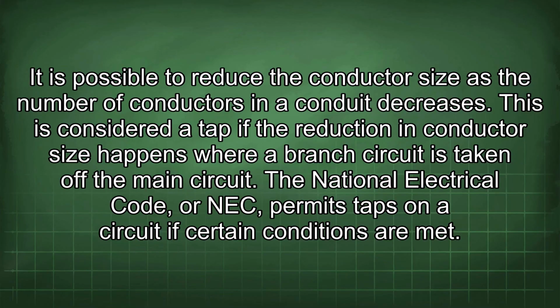It is possible to reduce the conductor size as the number of conductors in a conduit decreases. This is considered a tap if the reduction in conductor size happens where a branch circuit is taken off the main circuit. The National Electrical Code, or NEC, permits taps on a circuit if certain conditions are met.